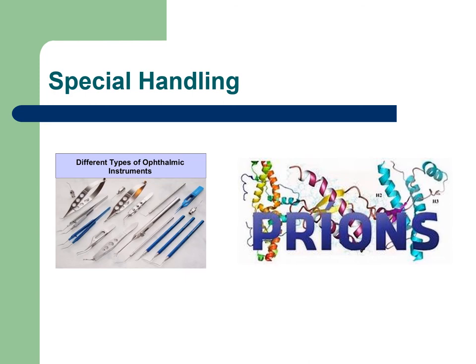The other option is a pre-vac at 273 degrees for 18 minutes. Option three is to immerse the instruments in a solution of NaOH and water for an hour, then rinse them, then steam sterilize for an hour. Or, immerse them in a solution of NaOH for an hour, then cook them for 30 minutes at 121 degrees Celsius, then clean them, then sterilize them again.